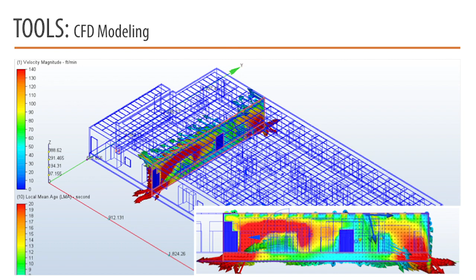Here's another example output from a project we're working on. We sliced a section isometrically through this room, looking at a 2-foot raised floor, with all the air coming out of the ceiling. The red is too high velocity, and what we found is that with this perforated raised floor system, all the air races one way and the other, creating a dead zone in the middle. That led us to finalize plans for extra large openings in the floor perforations, and for the outer thirds, floor tiles with dampers so we can throttle the airflow back and force more air to the middle. We're finishing up some modeling on this, and it's showing a much more laminar approach to air from the top down. Very powerful tool, and we're getting a lot of mileage out of it on many projects. You can figure it out before you build it, hopefully.